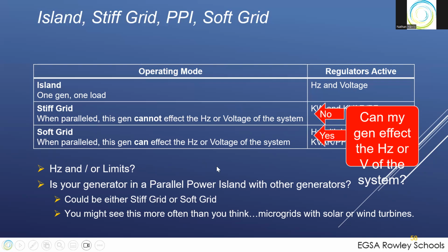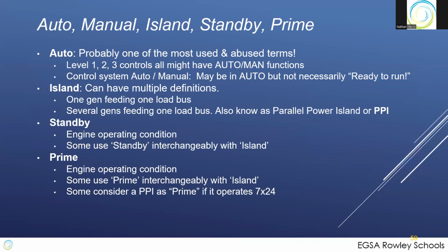And you're seeing this more and more. We're seeing this with the micro turbines, with wind turbines, with solar, things like that. We're seeing microgrids all over the place now, much more so than we did 20 years ago, as people bring on alternative energy sources. So you'll see these terms before. People use terms like auto, island, and standby prime. Keep in mind that standby and prime are really an engine operating condition. People use them as a power system condition, but really it's not. It's really an island mode, if you will. And it can be one generator in an island, or it can be several generators in an island.